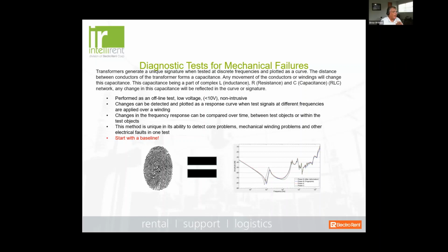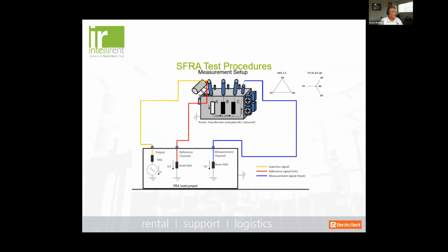But it is an offline test, a very low voltage. It's not intrusive, typically less than 10 volts. And then the changes can be detected and plotted as a response curve when test signals at different frequencies are applied over the windings. So changes in frequency response can be compared over time between test objects or within the test objects. In other words, we can compare an original trace to a new trace, but we can also compare traces between windings and between phases. But it's important, think of it as a fingerprint. Each transformer has its own fingerprint in terms of what that trace would look like when you first test it.